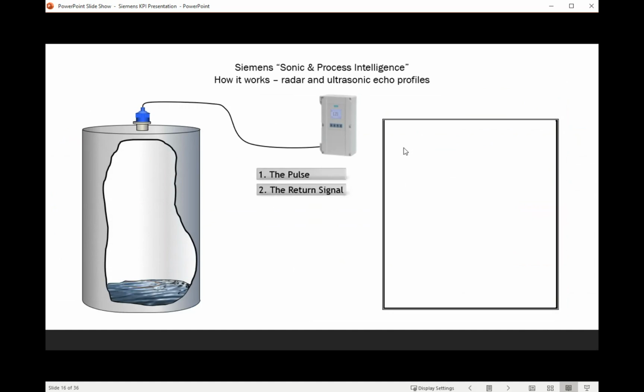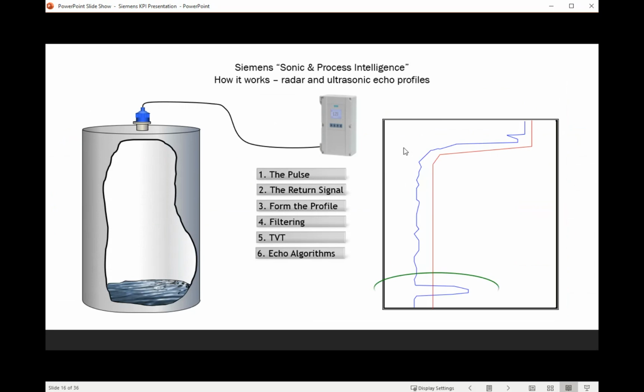Yeah, sonic intelligence really is the sequence of events of how a measurement takes place, and it takes place in about 7 steps. The ultrasonic controller is going to send out a pulse. That pulse is going to reflect off the material, and you're going to get a return signal.